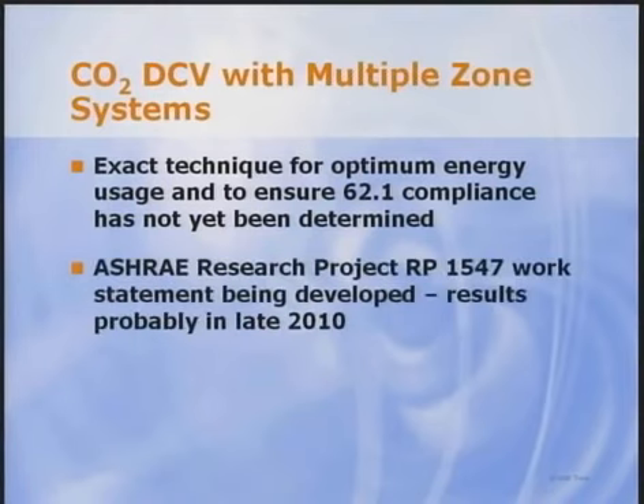But here's one approach that we do in our office. Based on limited modeling, we feel this logic will be optimum when the system has an outdoor air economizer. The logic is to take the CO2 signal range from CO2 max to the ambient and map the first half to increase the zone minimum airflow set point from what it would be without any people in the space up to the zone maximum airflow rate. At this point, the zone would effectively behave as a constant volume reheat zone.